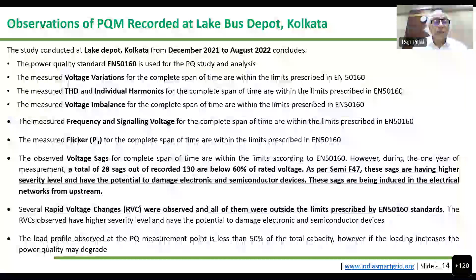Another serious thing which we noticed in Calcutta is rapid voltage changes, many of them outside the limits prescribed by EN 50160, which require more detailed studies. So RVCs we have not seen in Pune, but we have observed rapid voltage changes in Calcutta, and most of the RVCs observed were beyond the limits prescribed by EN 50160. The load profile observed at the PQ measurement here is also less than 50% of the total capacity. However, if the loading increases, there could be power quality degradation issues which need constant monitoring.